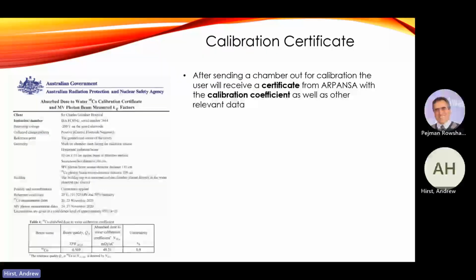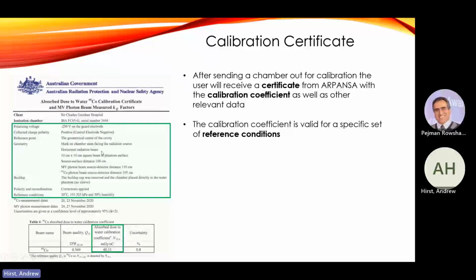Okay, so when you get your chamber back, you'll also get a certificate. This is really important, it has your calibration coefficient. Like I mentioned before, you can see this one's in milligray per nanocoulomb. It's important to note that this coefficient is valid for very specific reference conditions. They've listed their reference conditions of how they took the measurement here.